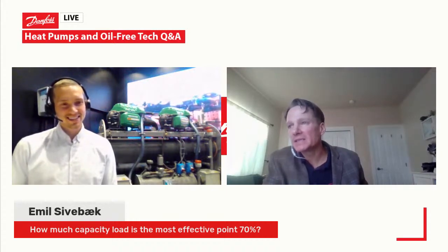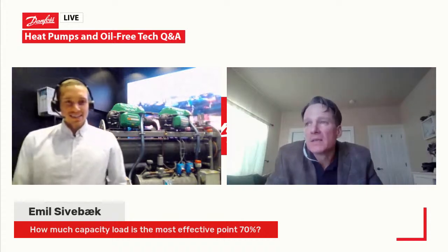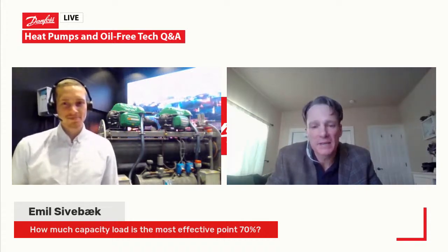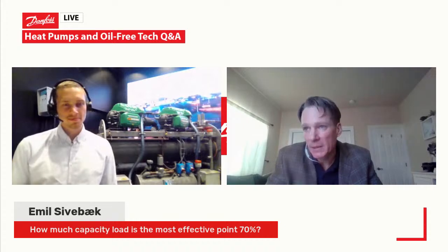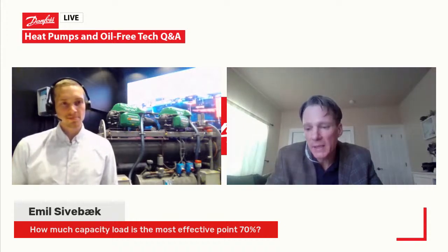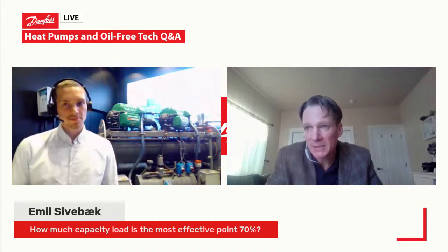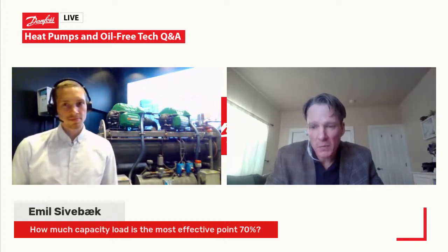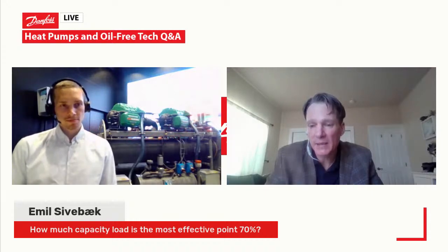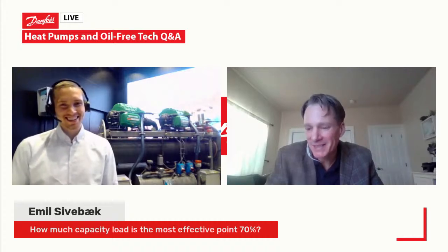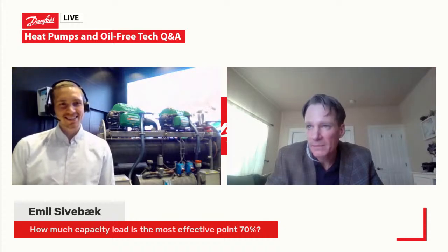In general, he's touching on something that's an important topic. The least efficient point, from the devil's advocate perspective, with an oil-free or Turbocore based system is always at the design COP. The payback you're going to get for an oil-free system, whether in a heat pump or chiller application, is going to be based on the off-design conditions. Part lift is more important than part load in terms of performance, but part load is important too. In general, the optimal point where you get the optimal efficiency of a Turbocore based design is at about 70% of the design capacity of that compressor. So you kind of had some insight there, mentioning the 70%, but that is roughly the optimal point.